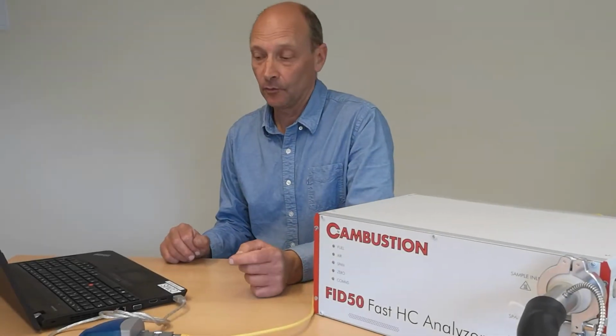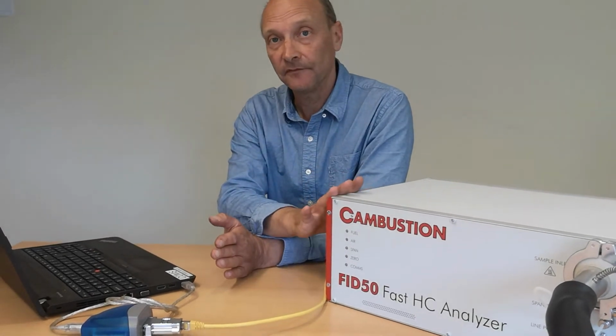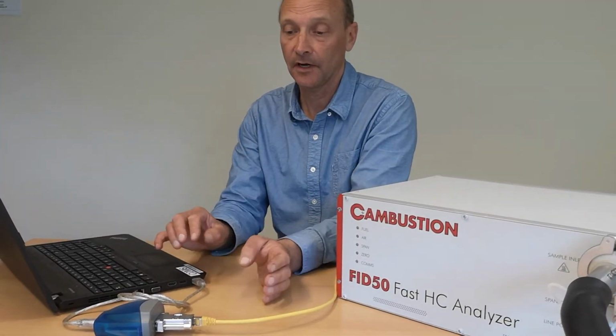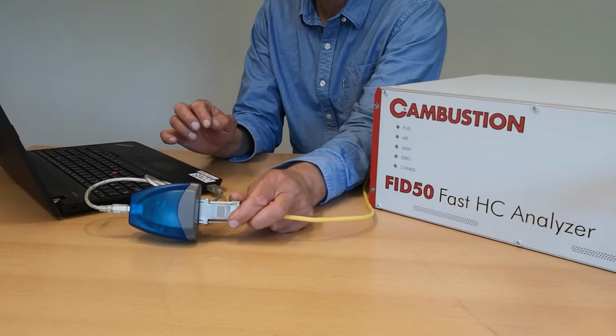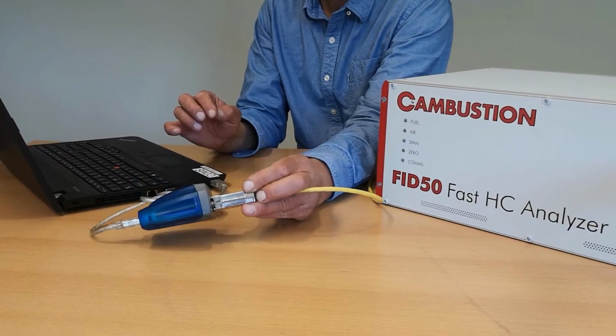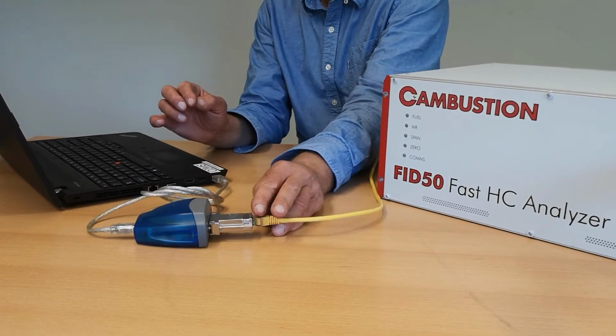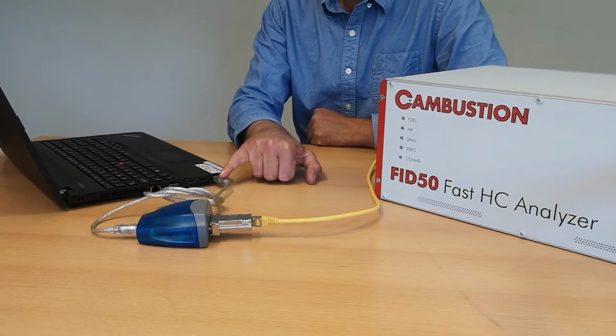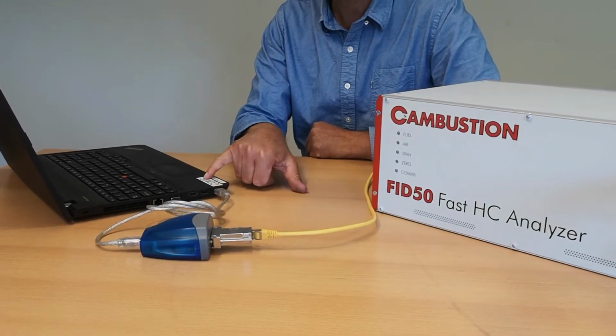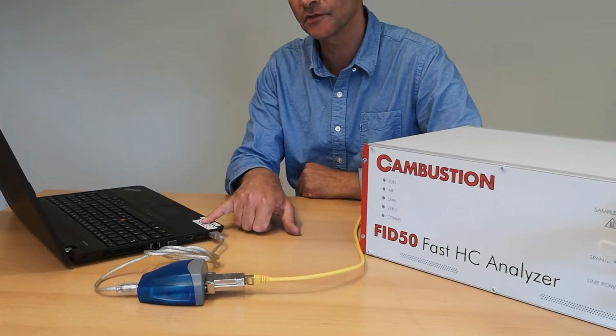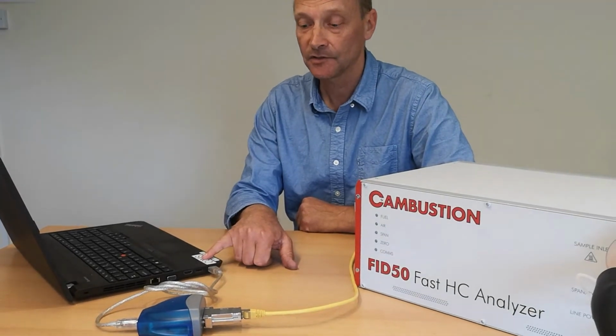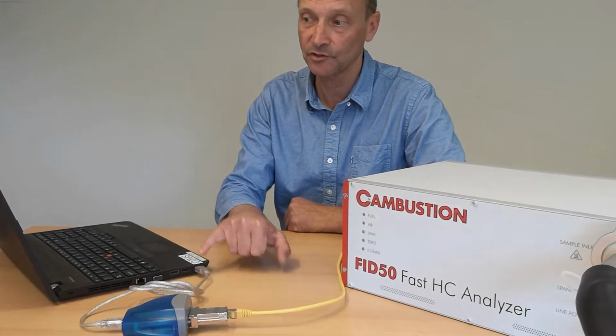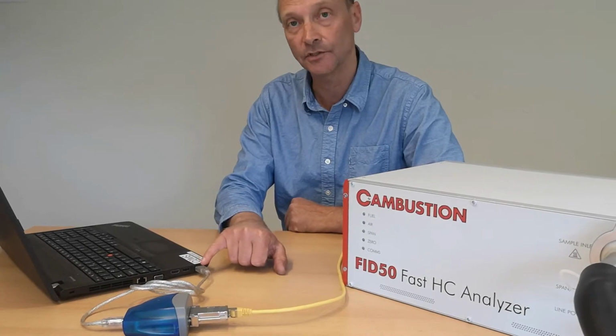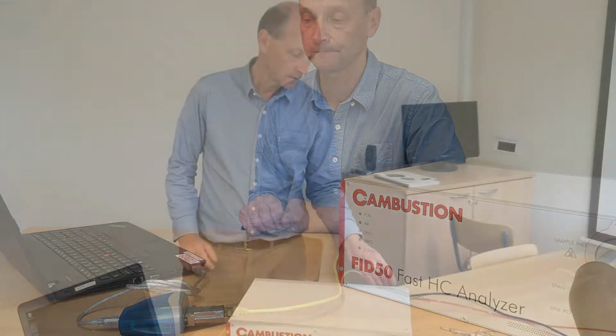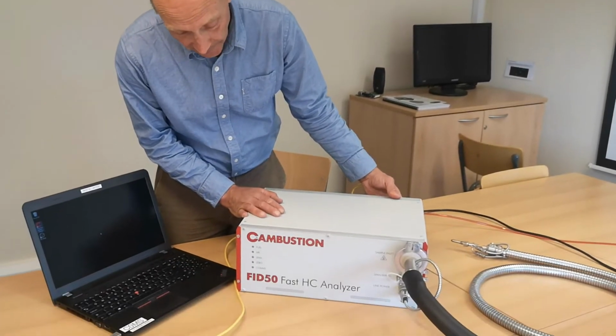In its simplest form, we can communicate with the FID50 via an RS485 to USB converter like this. And this is contained within the kit of parts sent with the instrument. We're attaching this to the part of the laptop which is labelled comms, and this has been configured to speak with the correct COM port which is allocated by the computer via the user interface. So we'll switch on the power to the analyzer.